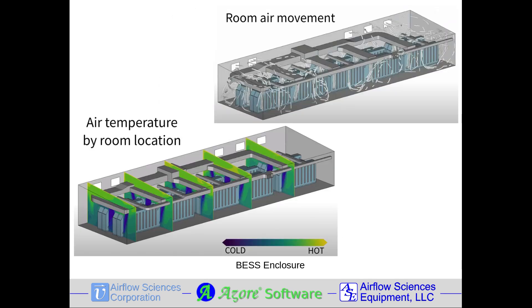Battery energy storage systems generate a significant amount of heat while both charging and discharging. Fans are often present on only one side of the enclosure, and as the racks of batteries heat up, hot spots with insufficient air exchanges may be present on the side opposite the air exchange units. A CFD model is very beneficial when designing enclosures for energy storage systems.